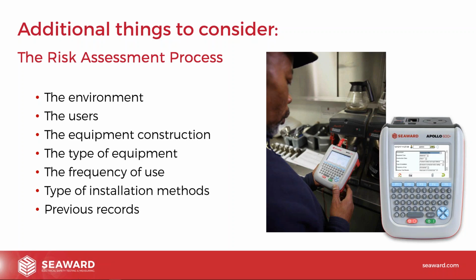But the most important one of all these, and I've probably hinted at it in the last few slides, is your previous records. Obviously your previous test records, using them to inform your test is a really powerful tool, and by doing that, you can actually make your testing more fit for purpose. 12 months is actually probably the wrong frequency for virtually everything, because it's too long really for high risk items, but it's probably too short for the low risk items. It generally tends to be this halfway house in the middle. So by using previous test results, we can actually tweak our frequencies to make sure that we've optimized the system so that the high risk items are being checked more often, the low risk items are being checked less often.